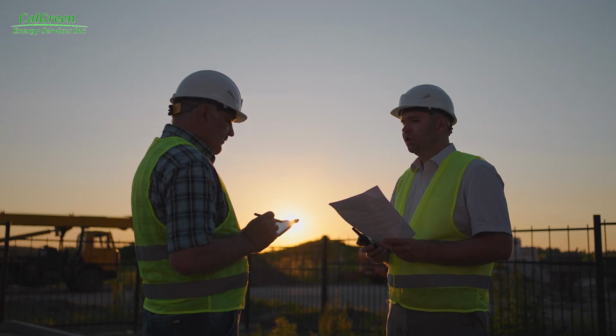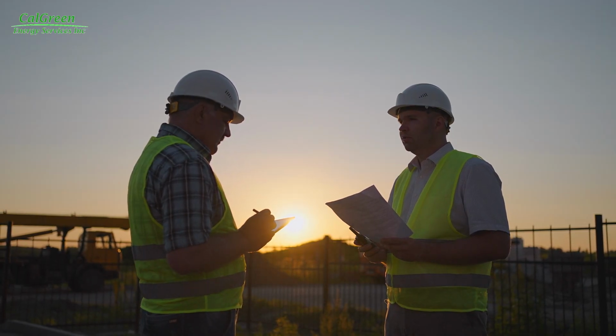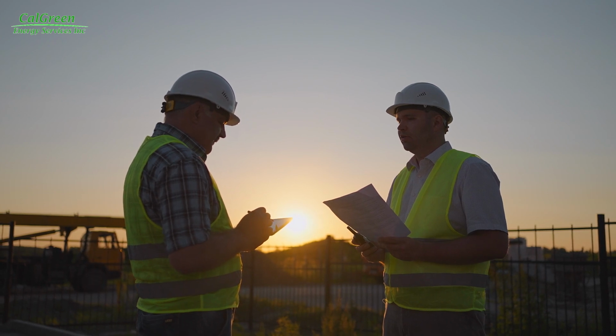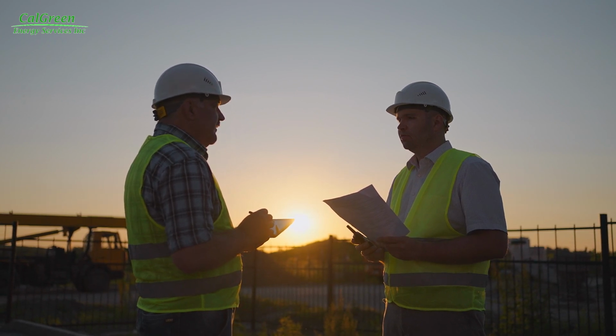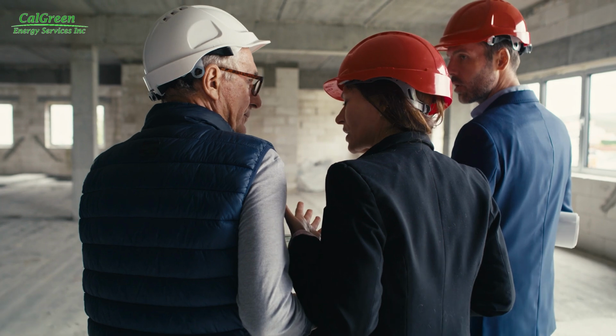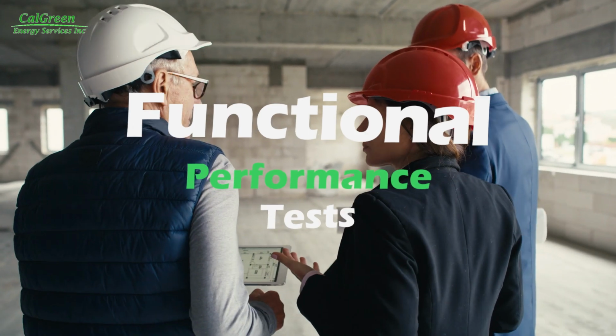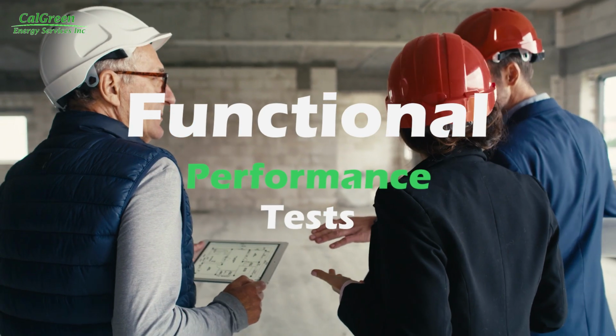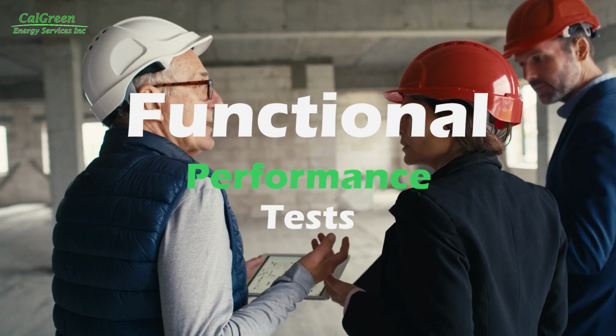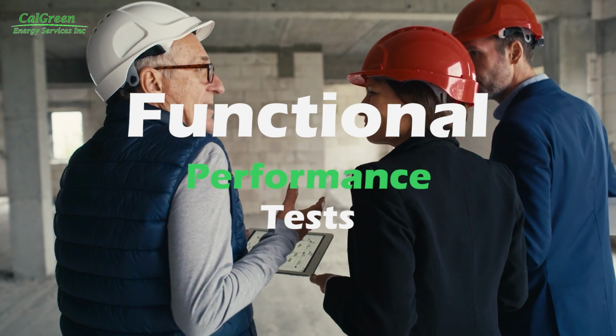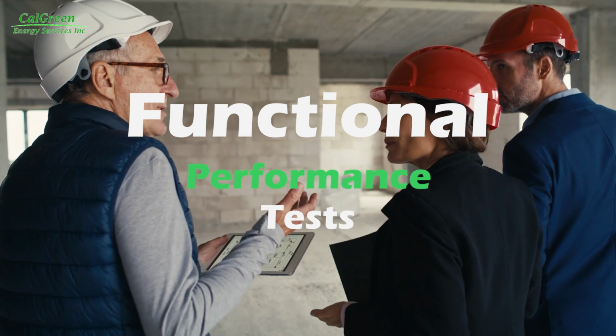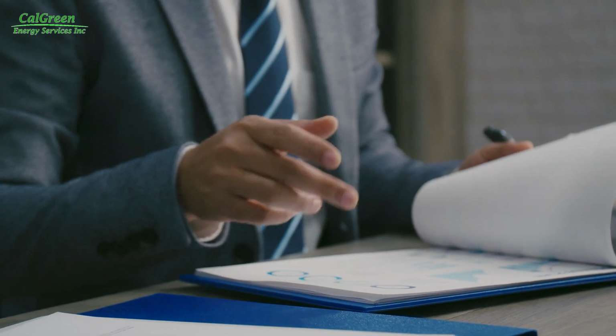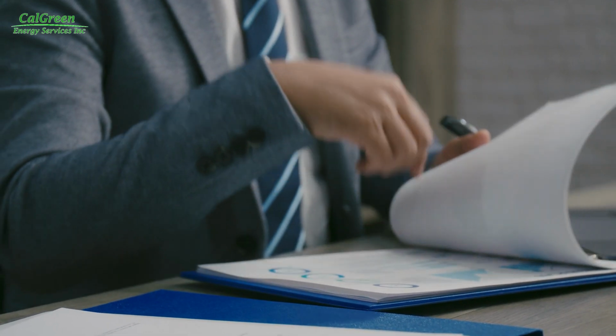Next, the commissioning coordinator reviews system submittals to ensure energy efficiency and compliance with the basis of design. They then author the functional performance tests, which are conducted once systems are installed, balanced, and Title 24 acceptance tests are completed. The final air balance report is also reviewed for compliance.